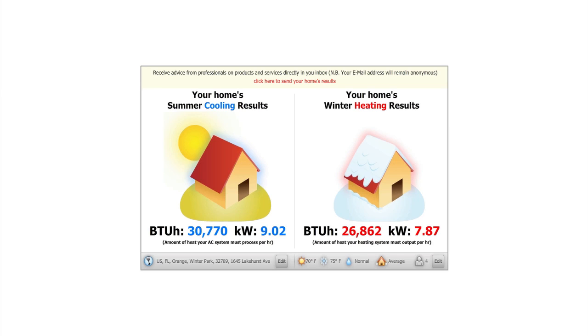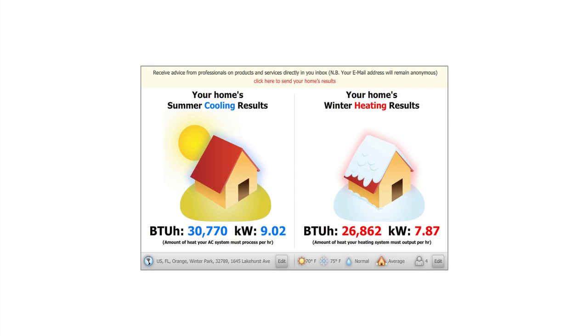A typical use case would start with a homeowner performing a calculation. You'll note that the heat gain and loss results are displayed automatically. Defaults for external climate, internal climate and the home's construction allow for instant results, leaving the homeowner to adjust these defaults to match their own. In this case, during the summer's hottest months, your AC system must process 9.02 kW of heat per hour. Similarly, your heating system must generate 7.87 kW of heat during your winter's coldest months.